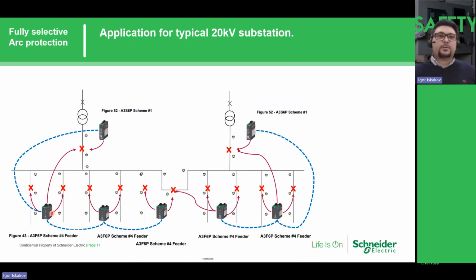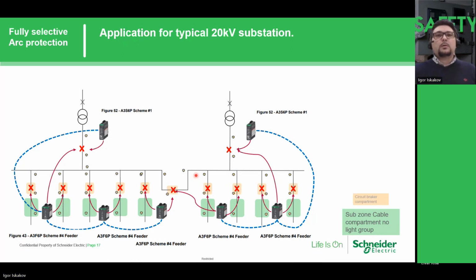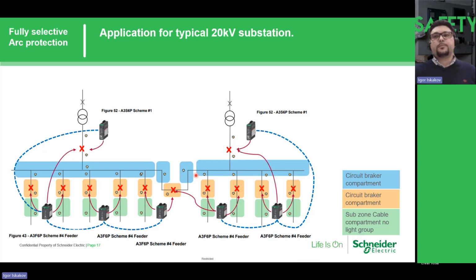This is a fully selective system when we have a trip on the subzone, which is the cable compartment. This means that during an arc flash on the cable ending, we secure all our application, and we will be able to trip only this exact feeder where we have the arc flash protection. By securing the circuit breaker compartment and the bus bar compartment, sorry, here's a mistake, we are able to send a command by our internal communication bus to the upper level unit.